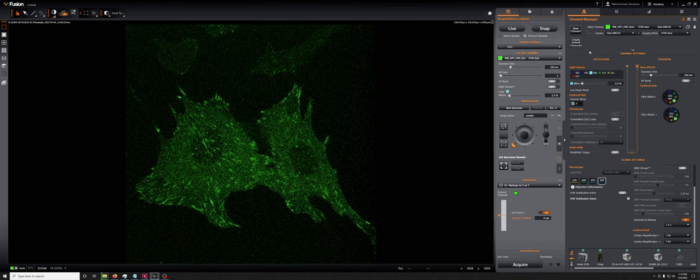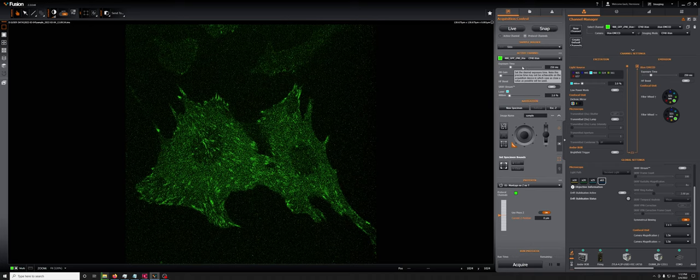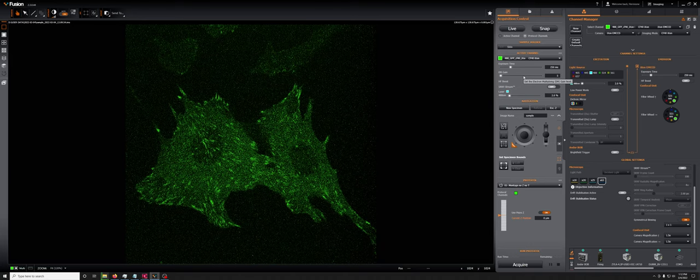So how do you actually make the most of the EMCCD? Just like the Zyla, the parameters that you can adjust are the exposure time and the laser power in the channel, but there is now this other parameter called EM gain.